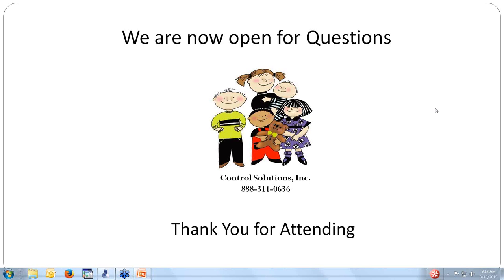Ms. Bond, it looks like your question was about calibration. What we've done here at Control Solutions is taken your logger and the probe you received, and we have a precision water bath system, several of them actually, and we calibrate your logger at 5 Celsius and minus 15. The accuracy of our water bath is 0.005, and the accuracy of the logger you have is 0.3 Celsius or better. The calibration certificate came with each of your boxes, and you need to keep it. It's a document compliant with our calibration standard, ISO 17025.